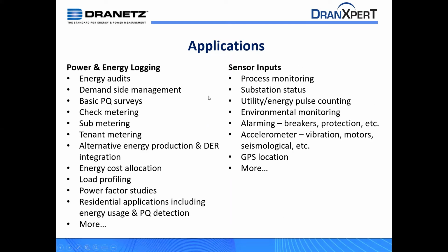Now, when you have the available sensor input module, well, then you add process monitoring, substation monitoring, because now you're looking at the condition of your environment. You have the ability to look at what's happening in parallel: transformer temperatures, alarms, status indicators, breaker positions, things like that. Pulse counting. So when we talk about energy, we in this field automatically assume electrical energy. Well, DranXperT using the digital inputs can certainly accumulate a counter from an electric meter, but it could be any form of utility, water, gas, steam, anything that's a pulse output and scaled can be measured and logged and even triggered by DranXperT.